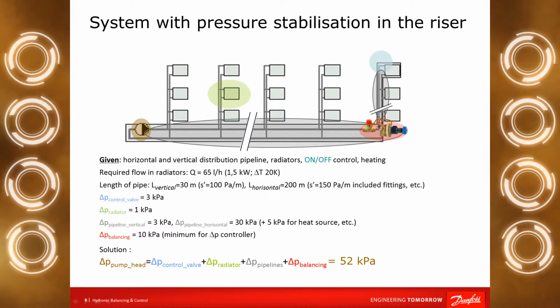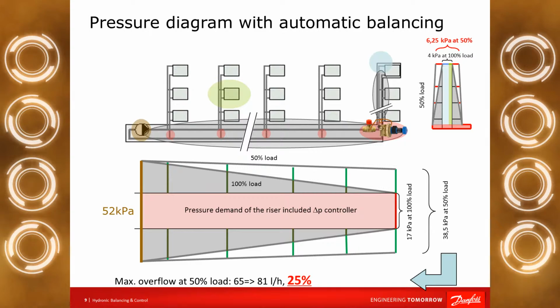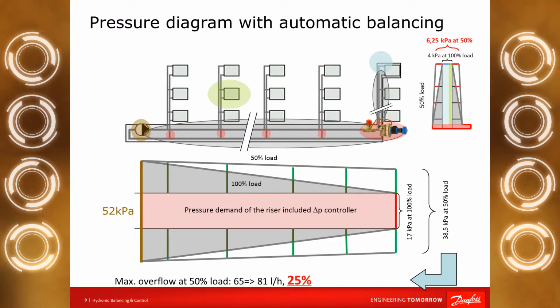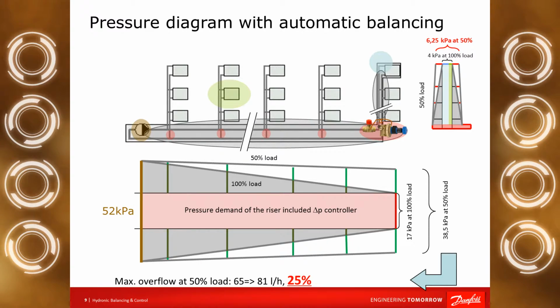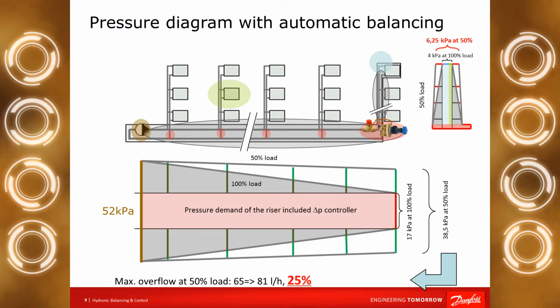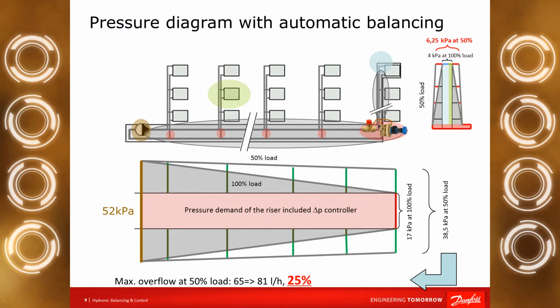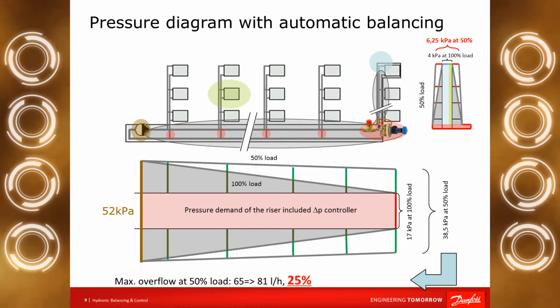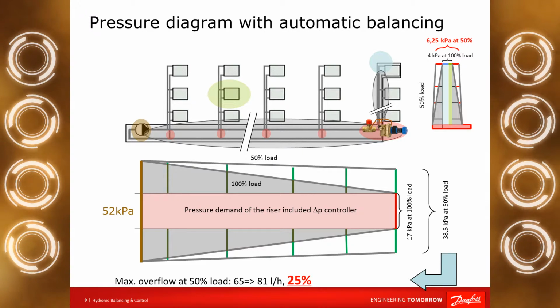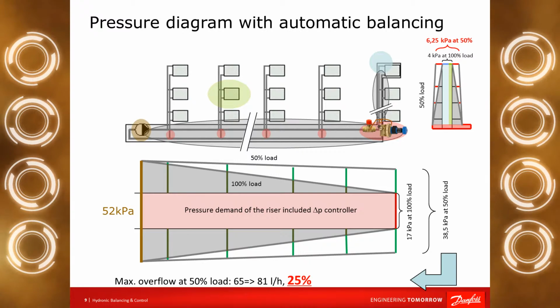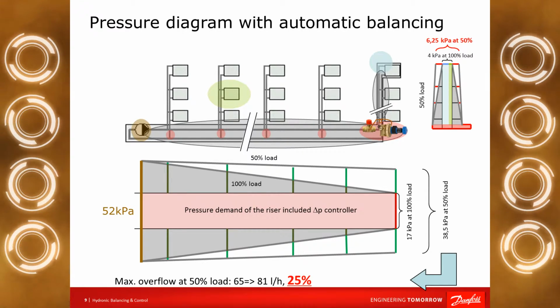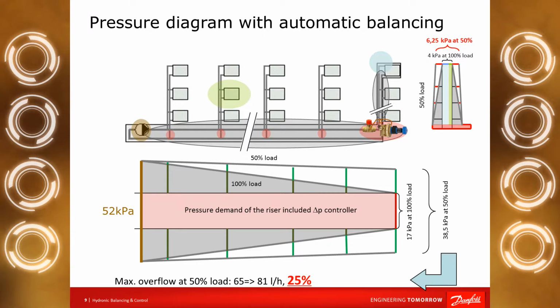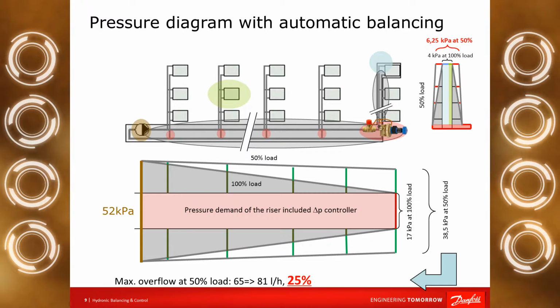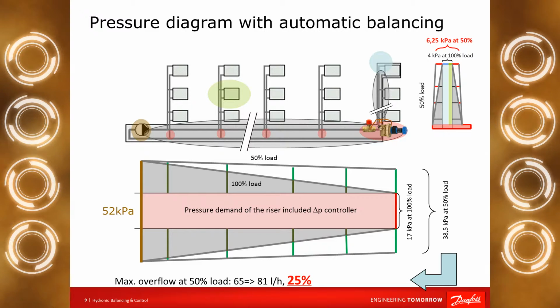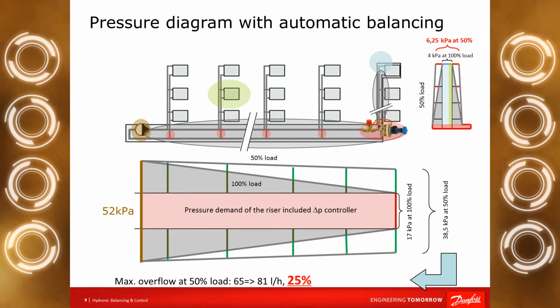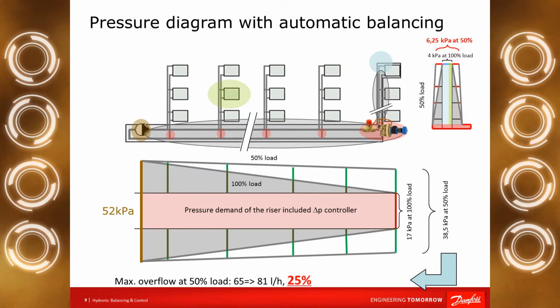Let's check how we modify the pressure diagram of the system with usage of the delta P controller. The basic situation is exactly the same. We have a commissioned system with pressure drops in different places, but now if we use a delta P controller in the bottom of the riser, we don't have to use manual balancing because this delta P controller will automatically set itself and reduce the unnecessary pressure that we can experience in the beginning of the distribution pipeline. If we use a delta P controller, definitely we will have overpressure on the distribution pipeline, but the delta P controller will simply remove it, and now we can see the unnecessary available pressure will arise only on the risers.